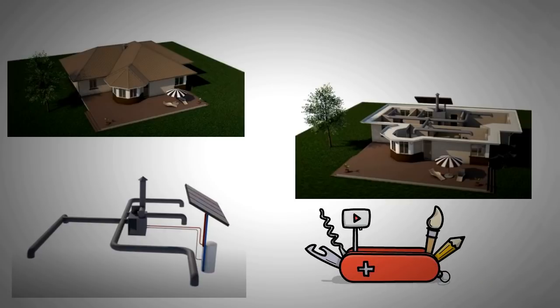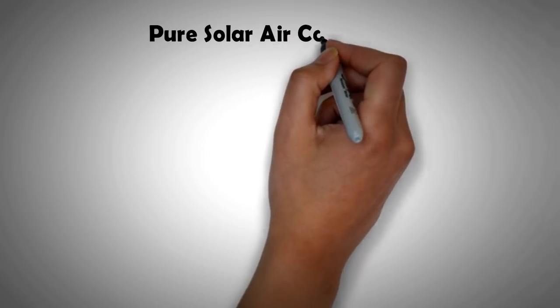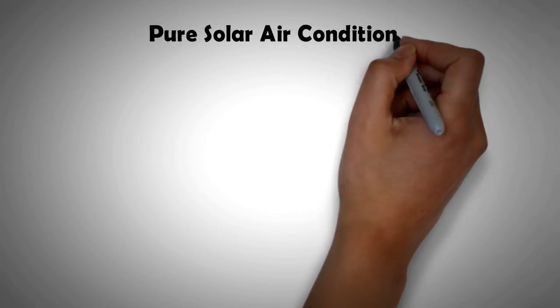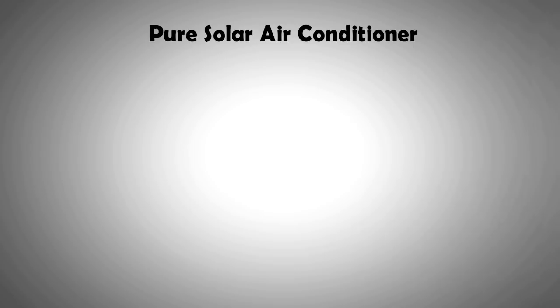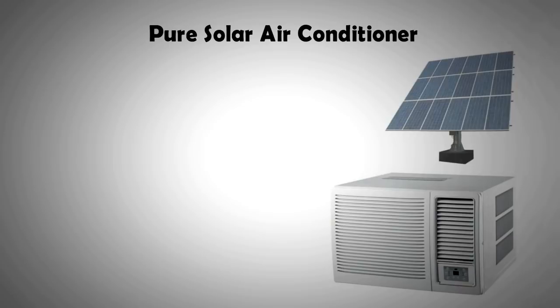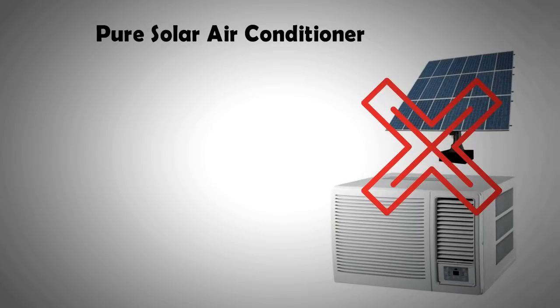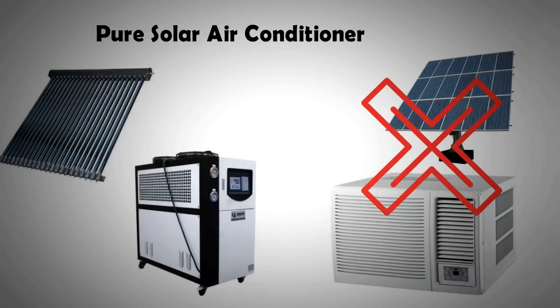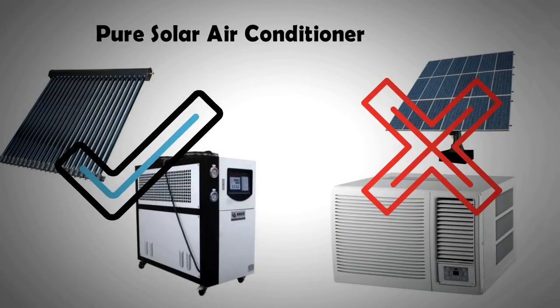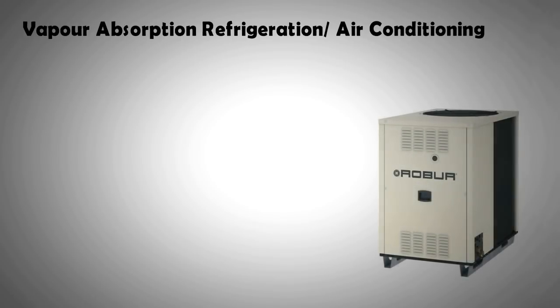Another thing that can be made is what I would like to call a pure solar air conditioner. I'm not talking here about the normal air conditioner that uses a vapor compression cycle and most people think that powering this AC unit with solar PV panels is what solar air conditioners are. No, I'm talking about vapor absorption cycle that has no compressor at all and uses heat as an energy source. Yes, this system has been used for refrigeration and air conditioning for a long time. It's just relatively unknown.